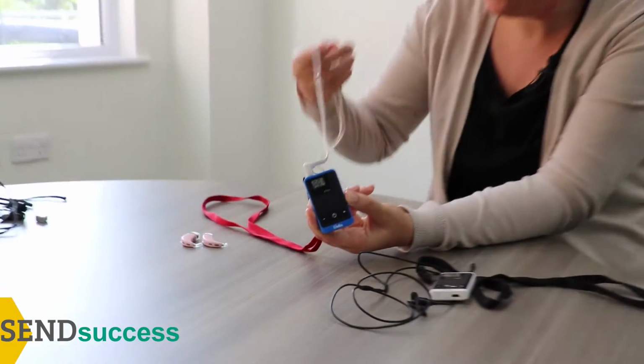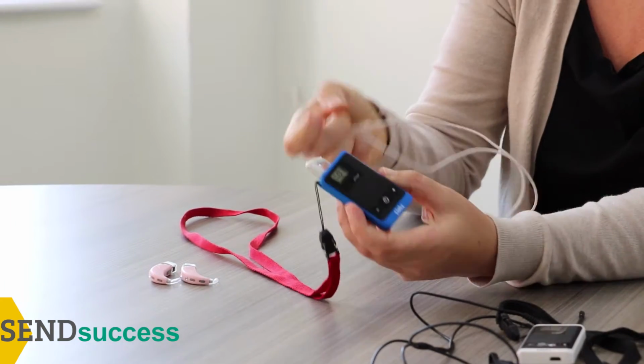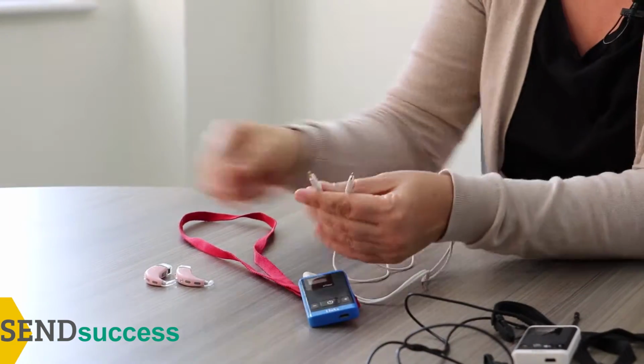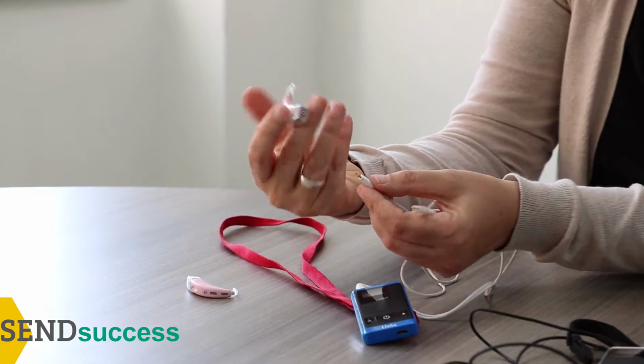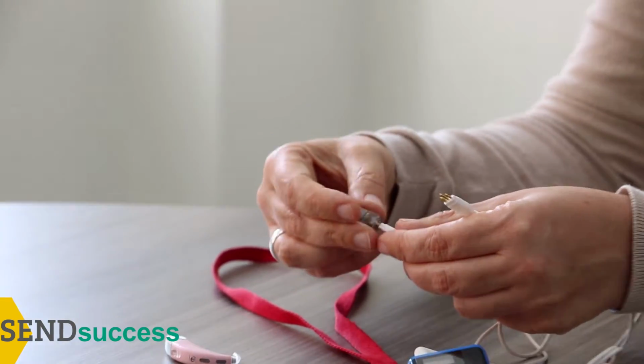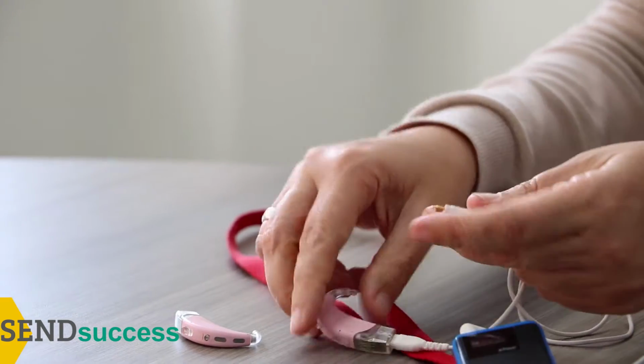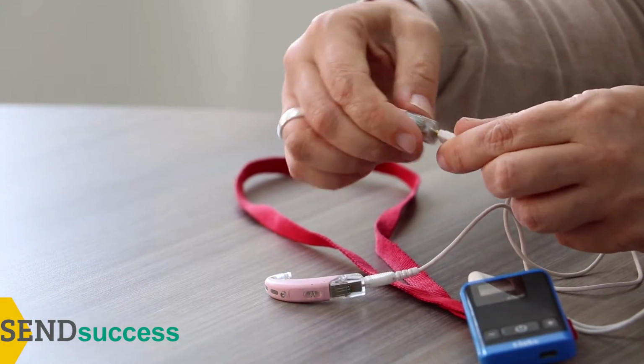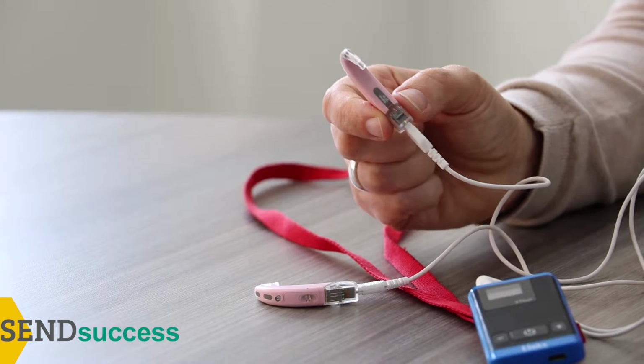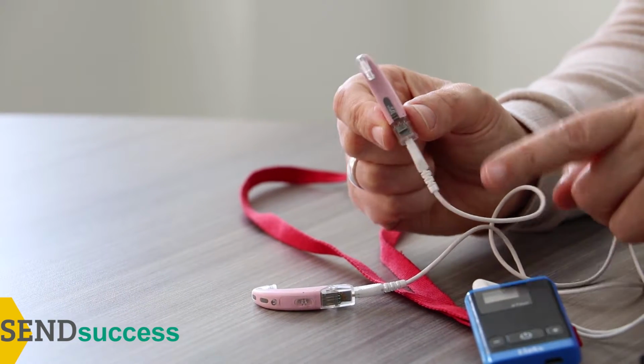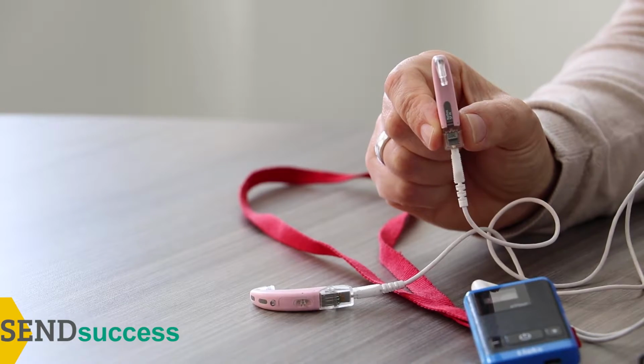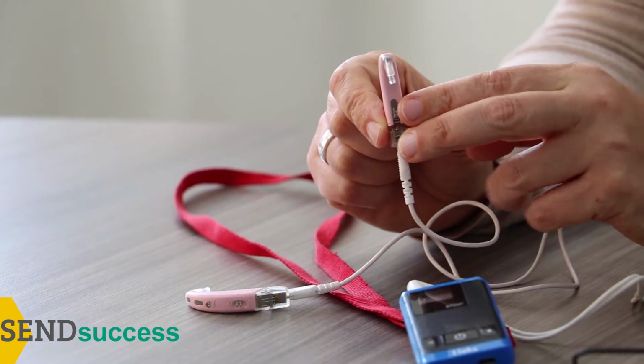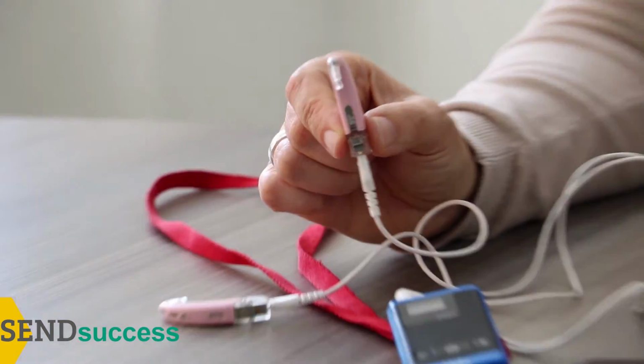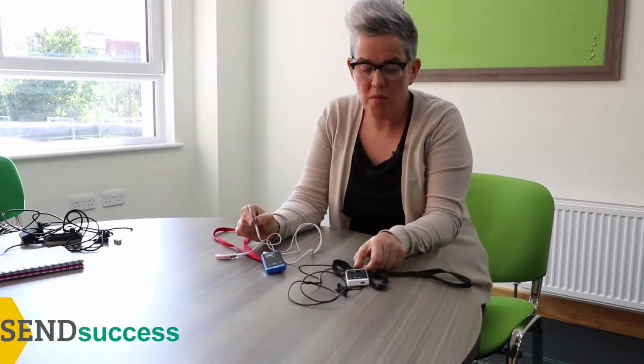As part of the receiver, they come with audio input leads. These will plug directly into the audio input shoes on the hearing aid user's hearing aids. Once clipped into place and both devices are on, then the hearing aid wearer should be able to hear the person speaking very clearly. To check this, it's always worth stepping outside of the room and asking a question and see if your hearing aid wearer can answer it when you come back into the room.